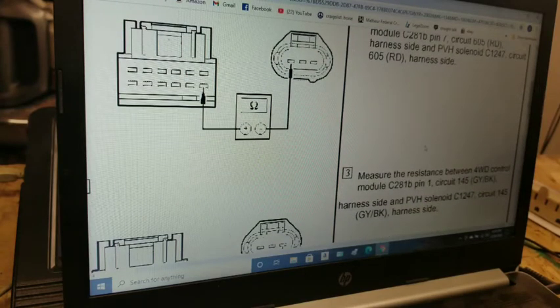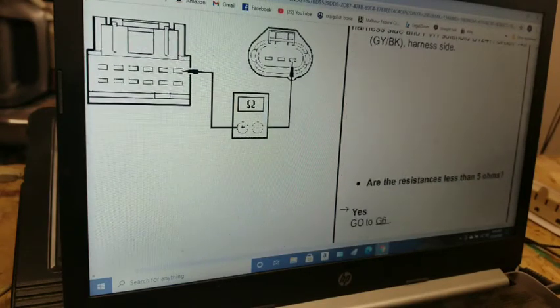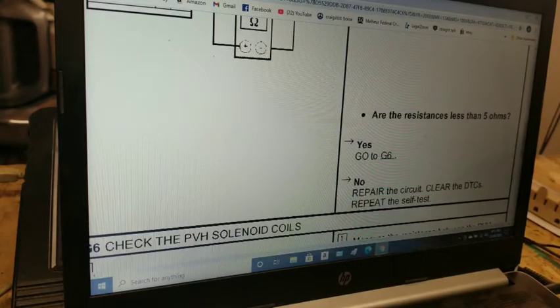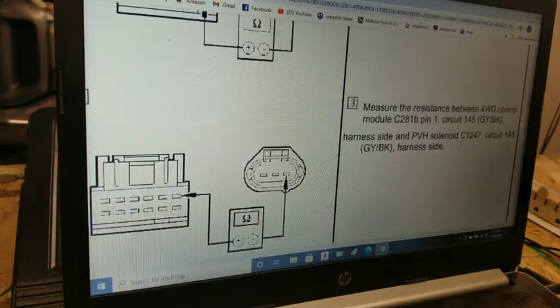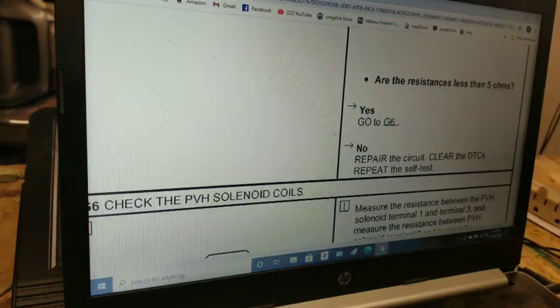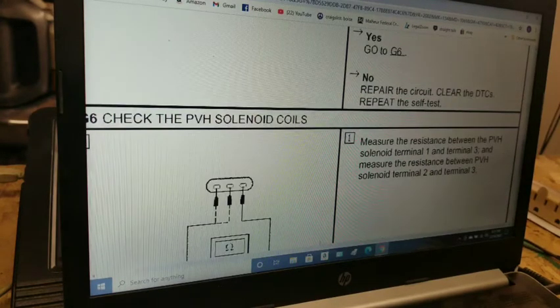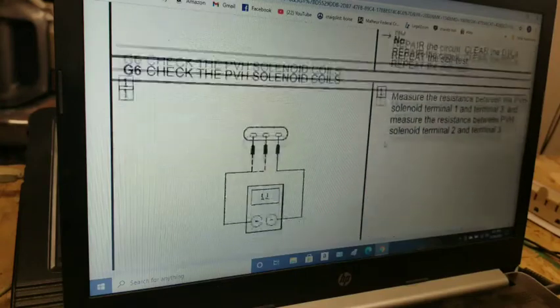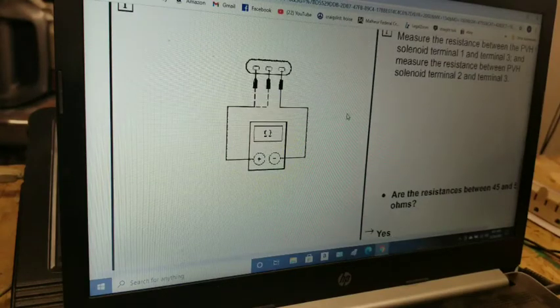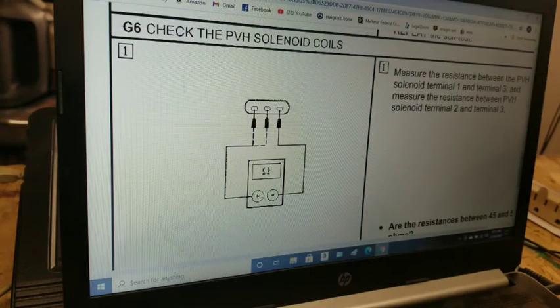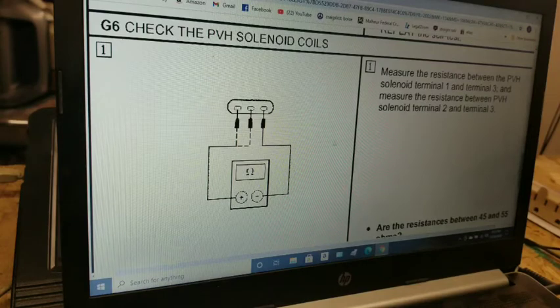When we measured this, the resistance was less than 5 ohms, meaning the wire between this pin and this one is good. If not, you'd repair the circuit, and it should be setting a diagnostic troubleshooting code that we established earlier. So next we check the PVH solenoid coils themselves.